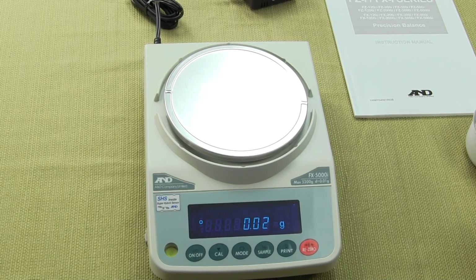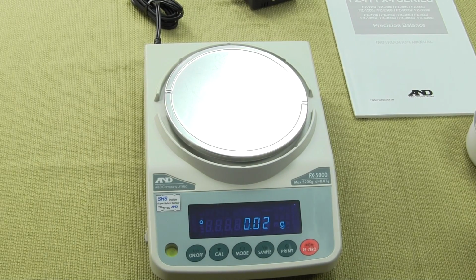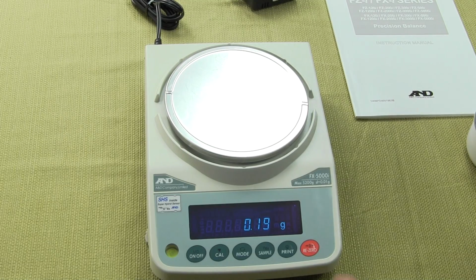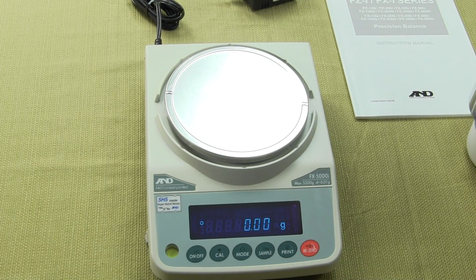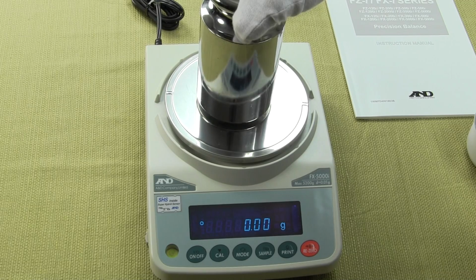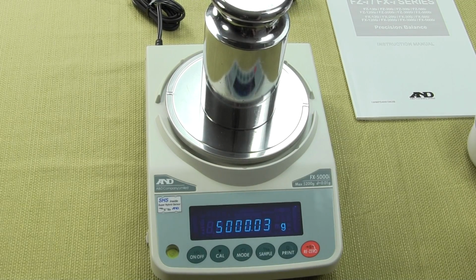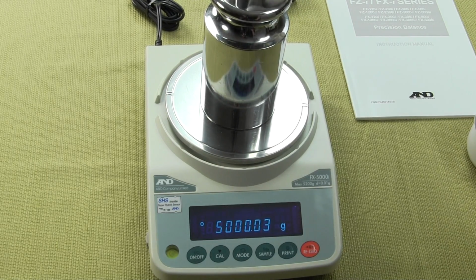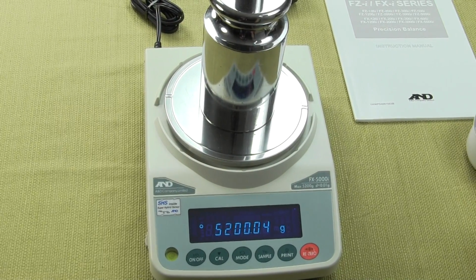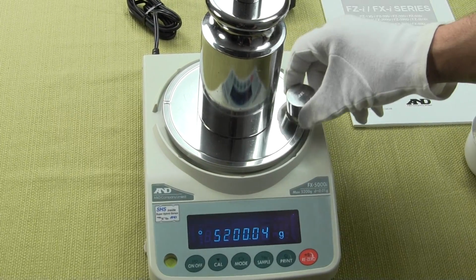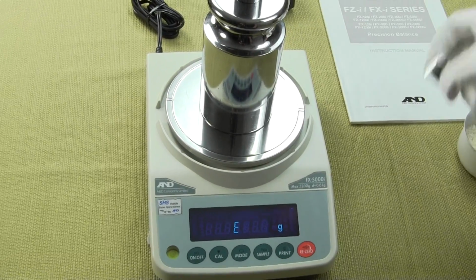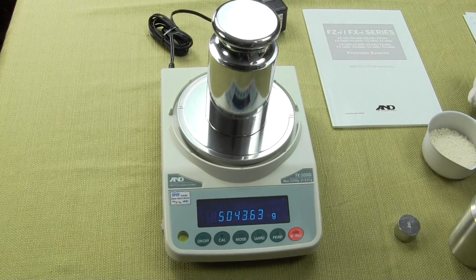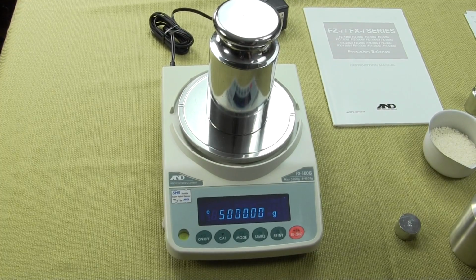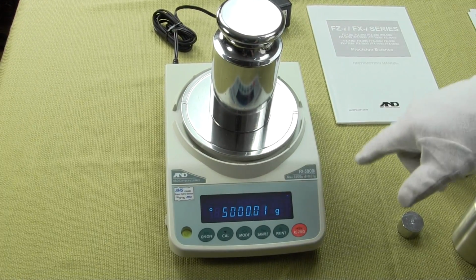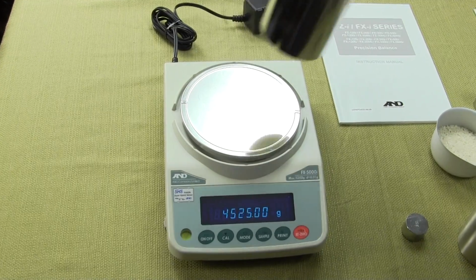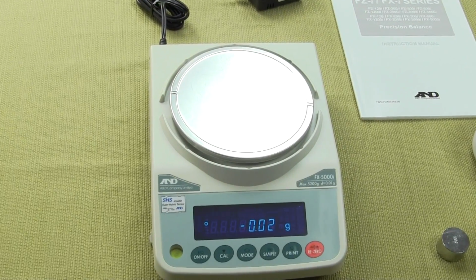Again, this balance has 5,200 grams by a hundredth of a gram. So we'll tare the balance - I have 5 kilograms, and here's a 200 gram weight. You'll see if we put an excessive load on it, anything over that, you get an E for overload. So you have 5,200 grams by a hundredth of a gram, and this balance in particular can be calibrated with either a 3 kilogram, 2 kilogram, 1 kilogram, or 500 gram weight.